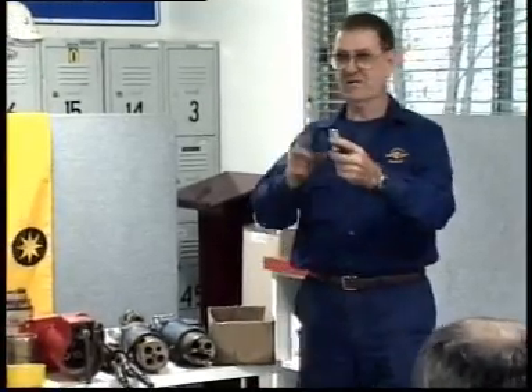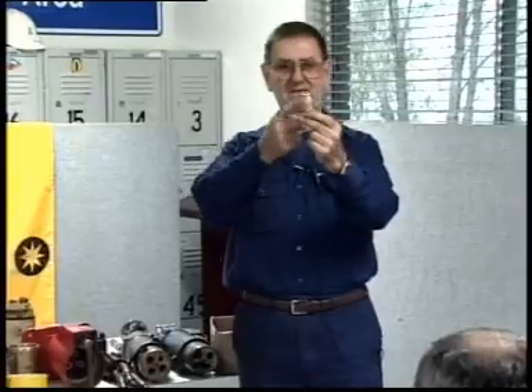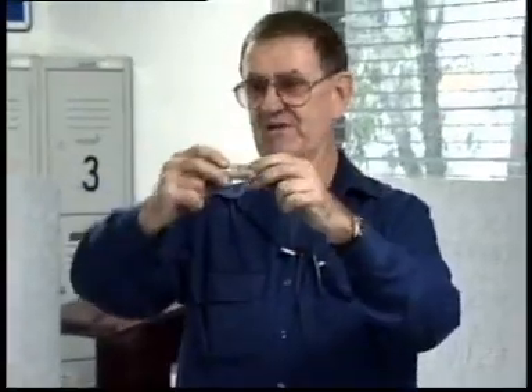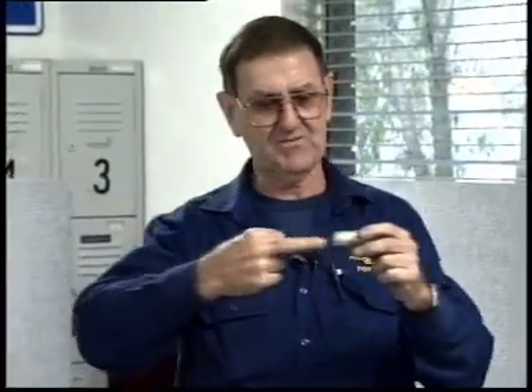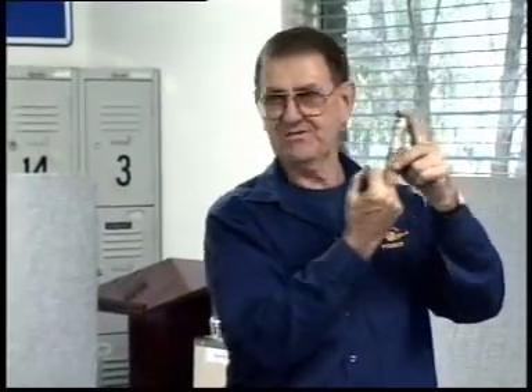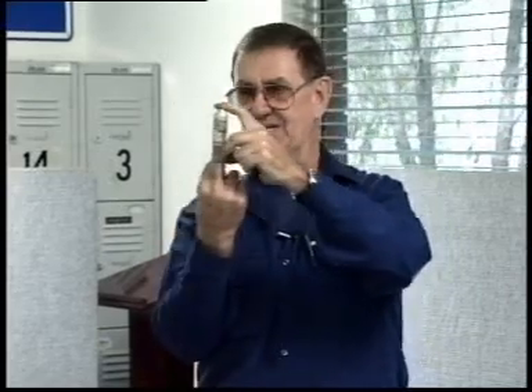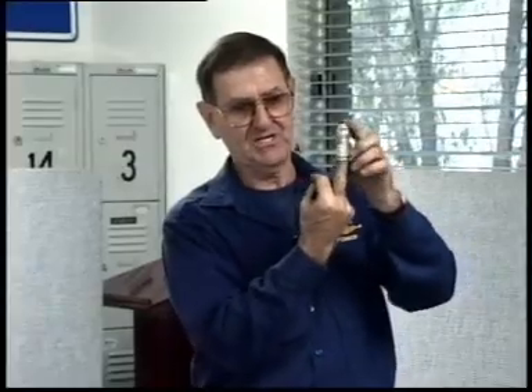Now, these things have got a spring around these fingers. These are split fingers that go down these contacts, and they've got a spring around the end of them. The spring's there so that when the male pin goes in there, it maintains pressure on the male pin and contact so you don't get any burning in there. If that spring's damaged in any way, and how it gets damaged, if water gets in the front end of the plug, it starts to rust the spring. When the spring starts to rust, then you don't have as much tension on those fingers anymore. So there's not as much contact pressure on the male pin, so it starts to heat up.